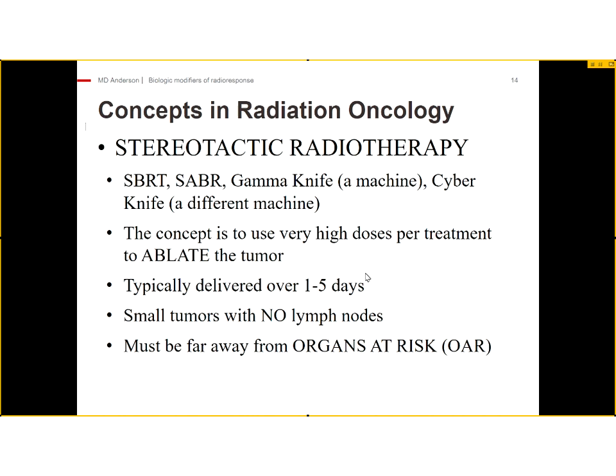So what happens is the physician inputs the plan. For Gamma Knife especially, you can do your own plan. You can drop shots, is what they call it. Okay, I'm going to drop a shot here, right around the tumor, here, right around the tumor, here, right around the tumor. But that is translated by the computer into where the cobalt source is going.